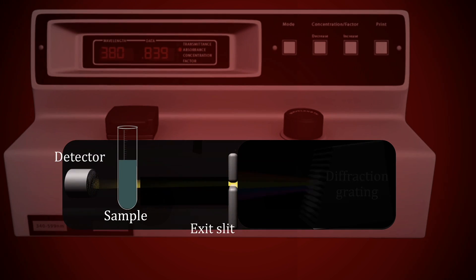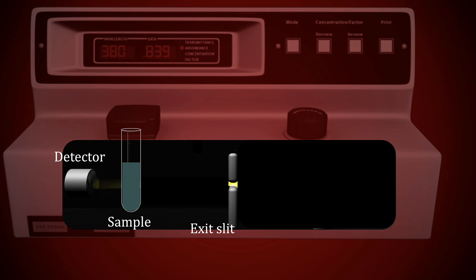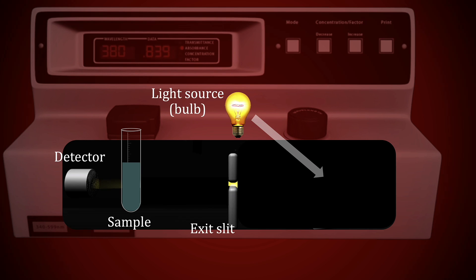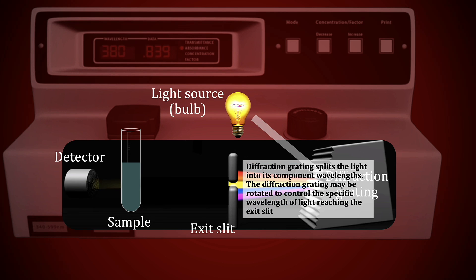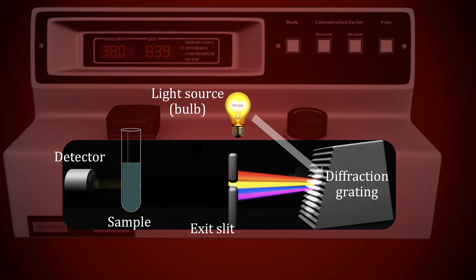Here's how a spectrophotometer works. A light source, typically a bulb of some kind, shines light on a diffraction grating which acts as a prism and splits the light into its component wavelengths. The grating can be rotated to direct the light towards the exit slit so that only light of a certain wavelength exits the slit and enters the sample.